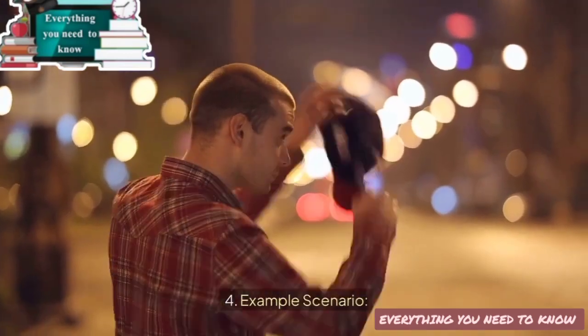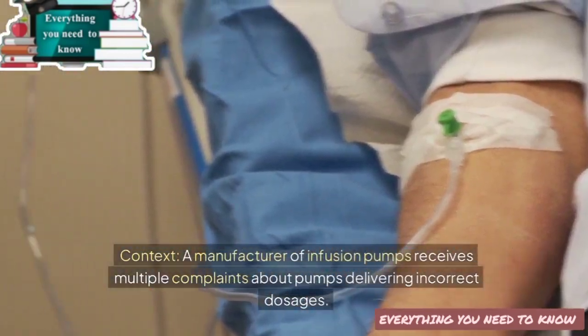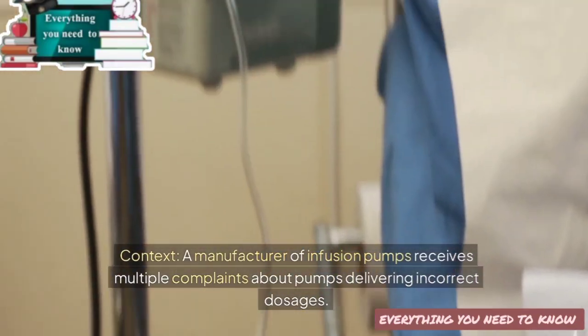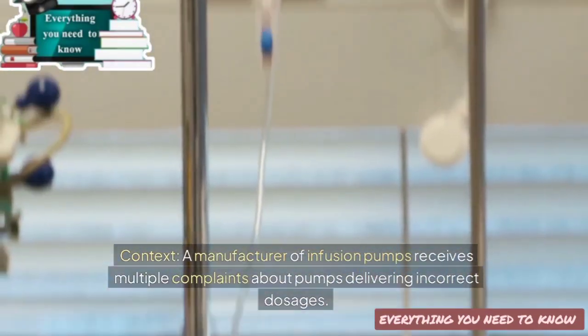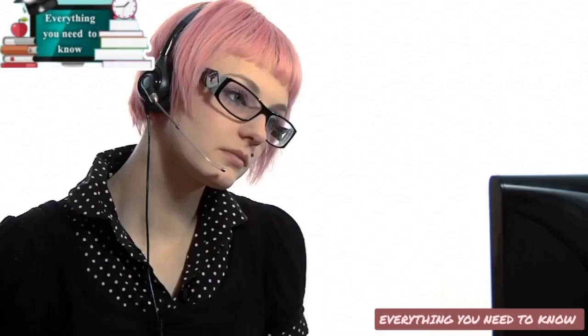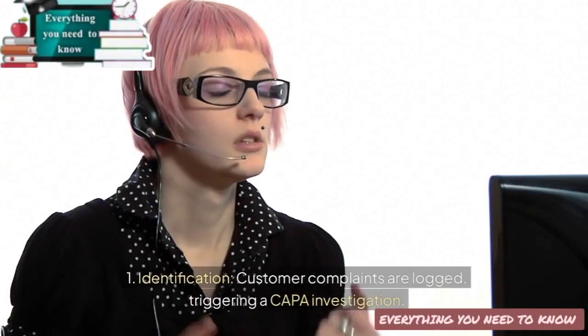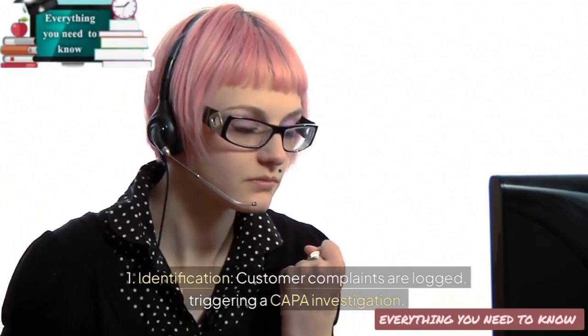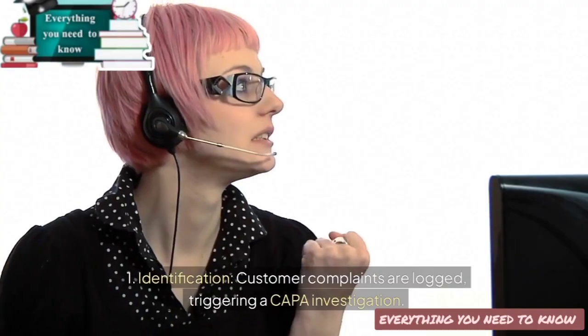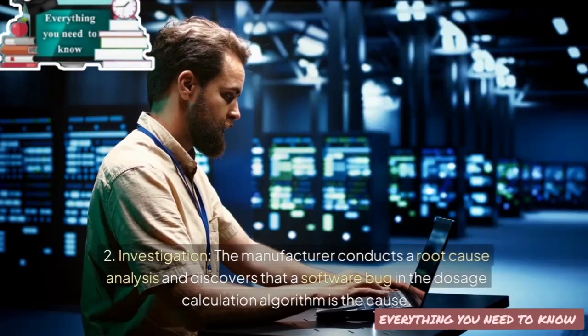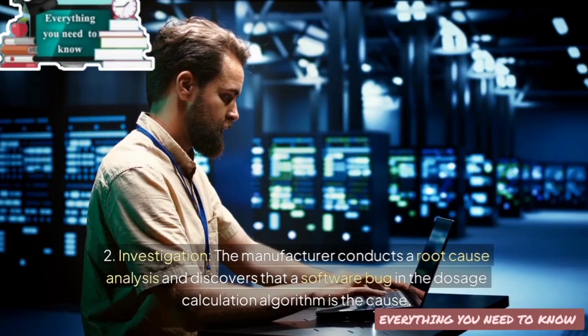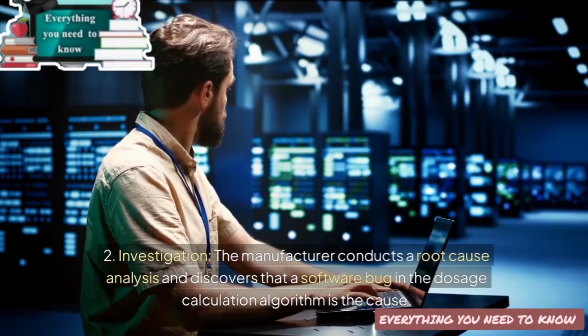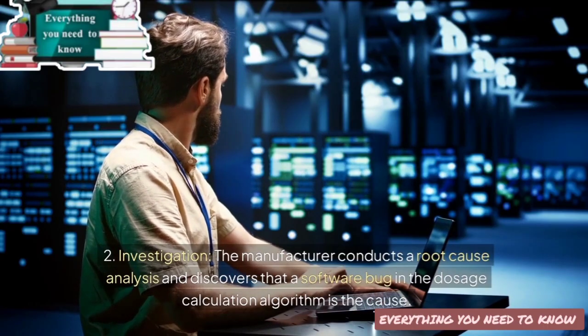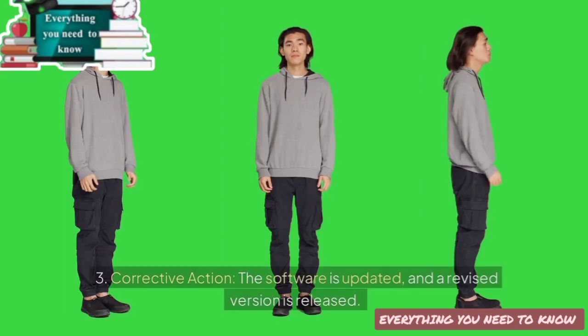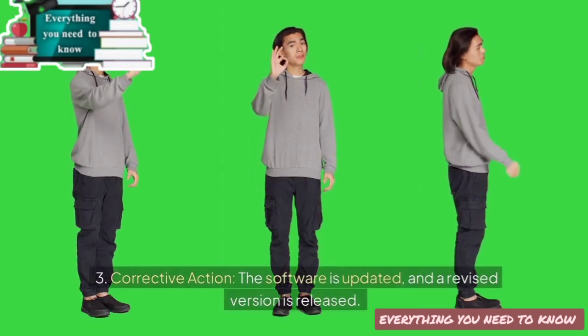4. Example scenario. A manufacturer of infusion pumps receives multiple complaints about pumps delivering incorrect dosages. 1. Identification. Customer complaints are logged, triggering a CAPA investigation. 2. Investigation. The manufacturer conducts a root cause analysis and discovers that a software bug in the dosage calculation algorithm is the cause.